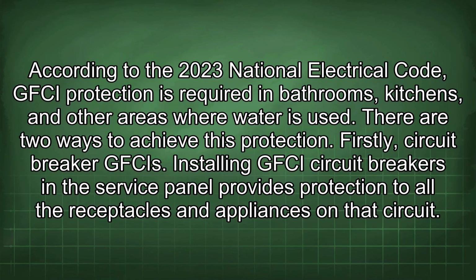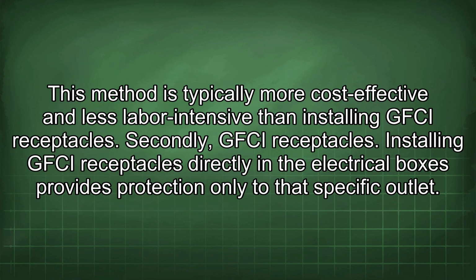According to the 2023 National Electrical Code, GFCI protection is required in bathrooms, kitchens, and other areas where water is used. There are two ways to achieve this protection. Firstly, circuit breaker GFCIs. Installing GFCI circuit breakers in the service panel provides protection to all the receptacles and appliances on that circuit. This method is typically more cost-effective and less labor-intensive than installing GFCI receptacles.